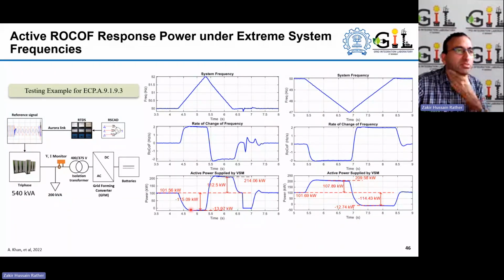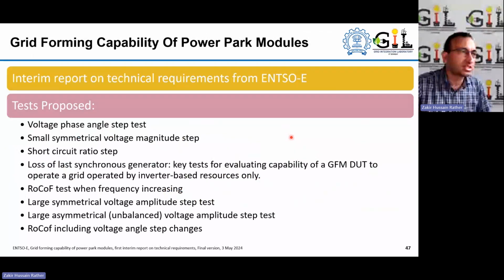This slide is showing some of the tests that are done, for example for the grid code regulation that I showed in the previous slide for grid forming. So this is the 2 hertz per second withstand capability in this case. And this is the power output, which is responding accordingly. Here is some current limitation that is coming into the picture. And this is the RoCoF requirement. Again, you can see the 2 hertz per second test for this grid forming technology.